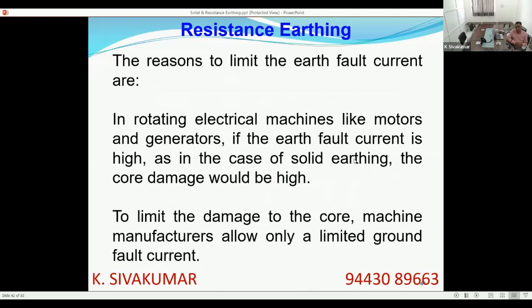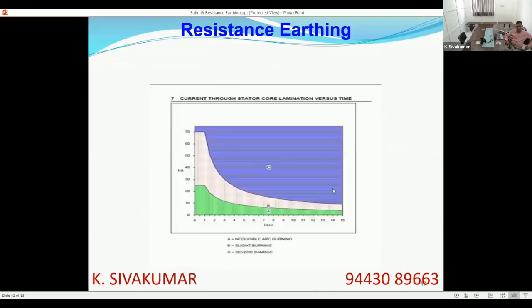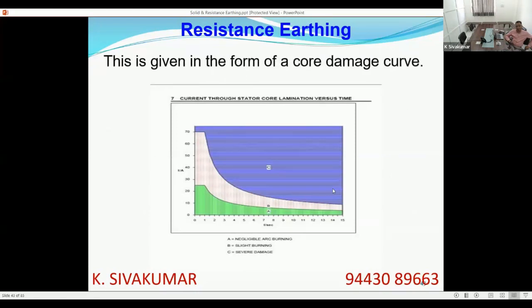The reason why you have to limit the earth fault current, the major reason, is that in rotating electrical machines like motors and generators, if the earth fault current is very high, as in the case of solid earthing, the core damage will be very high. To limit the damage to the core, if you ask, the machine manufacturer will give you a core damage curve. A limited ground fault current is allowed. This is given in the form of a core damage curve. So this core damage curve will look something like this. This I have taken from a motor manufacturer's catalog data sheet. You can see the x-axis is seconds, the y-axis is current. So how much current can it tolerate, and for how long?